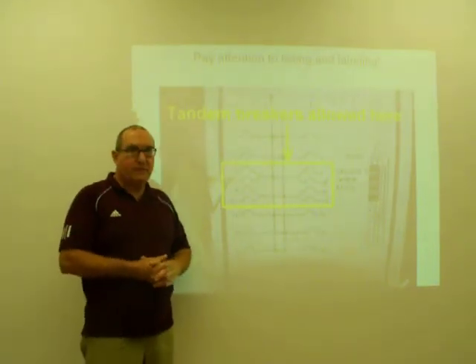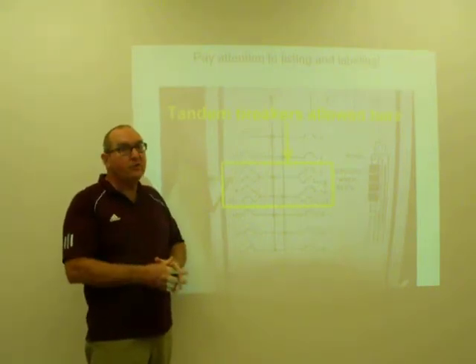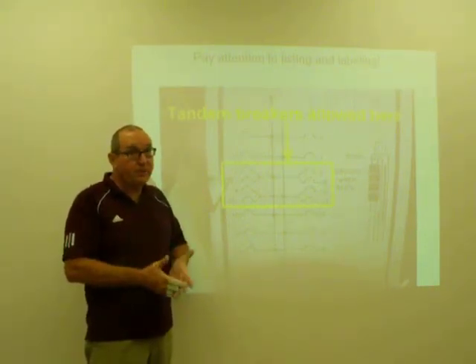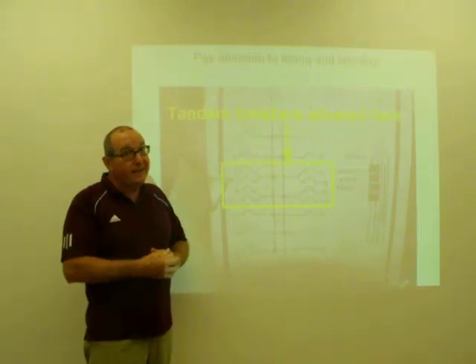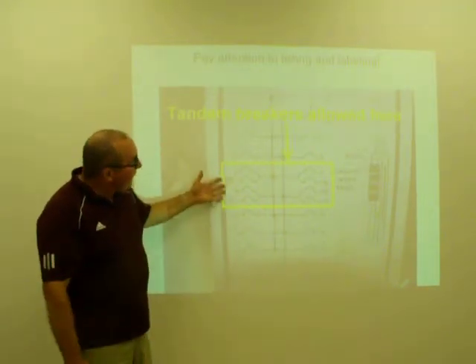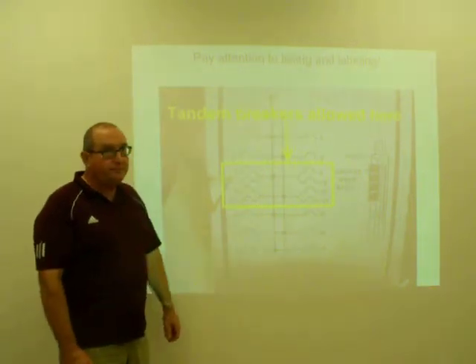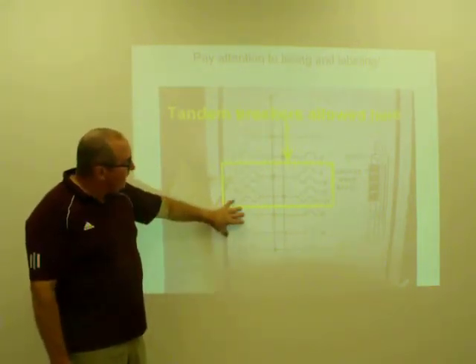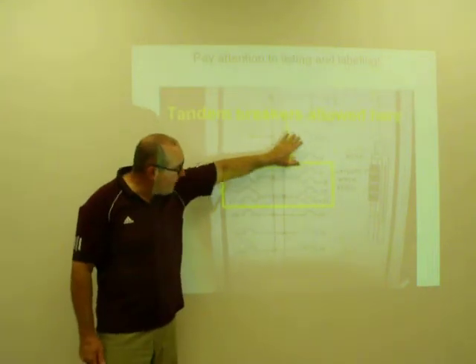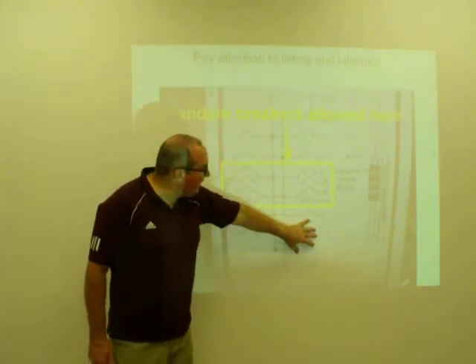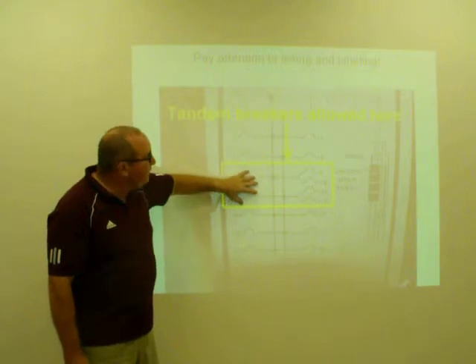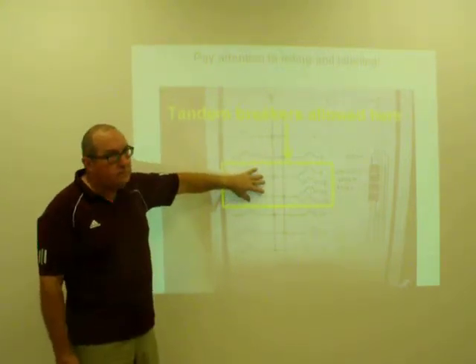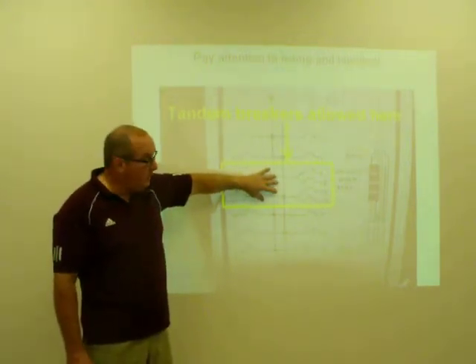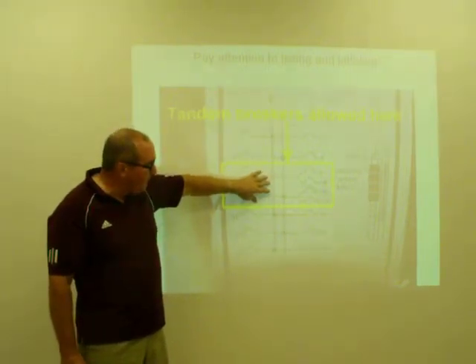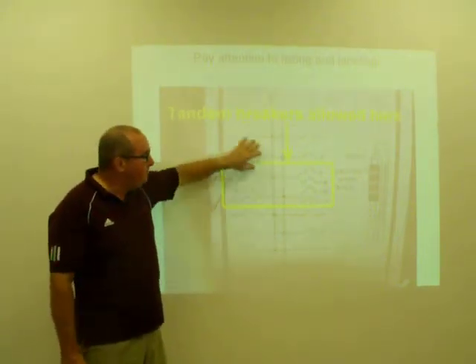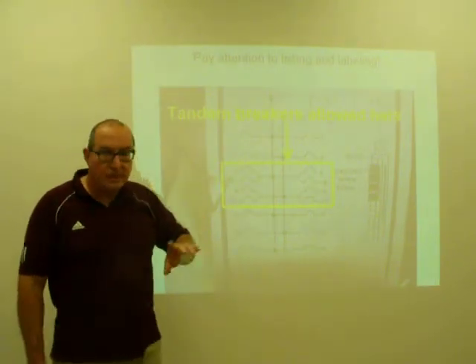Documentation in a panel board that reveals to the installer what the listing requirements are for this piece of equipment will typically tell you what you can and cannot do. So you'll have a diagram inside the cover that will show you, yes, I can put full-size breakers in these slots. I can put full-size breakers in these slots. I could put full-size breakers or tandem or half-size breakers in these slots.